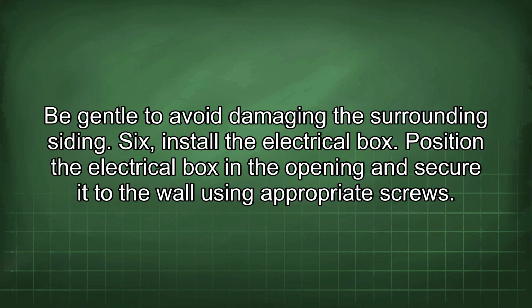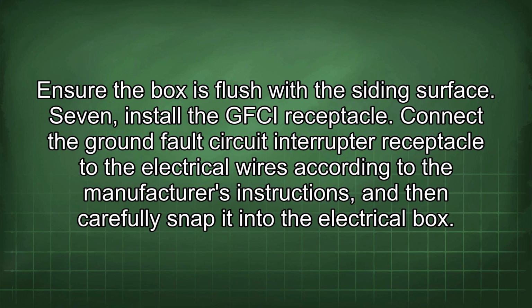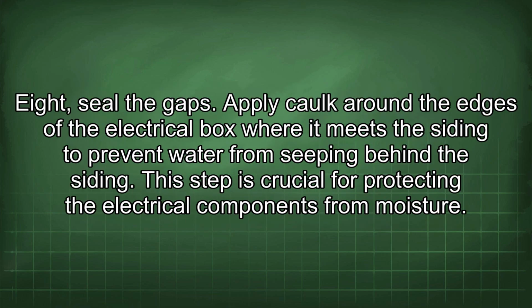6. Install the electrical box. Position the electrical box in the opening and secure it to the wall using appropriate screws. Ensure the box is flush with the siding surface. 7. Install the GFCI receptacle. Connect the ground fault circuit interrupter receptacle to the electrical wires according to the manufacturer's instructions, and then carefully snap it into the electrical box. 8. Seal the gaps. Apply caulk around the edges of the electrical box where it meets the siding to prevent water from seeping behind the siding. This step is crucial for protecting the electrical components from moisture.